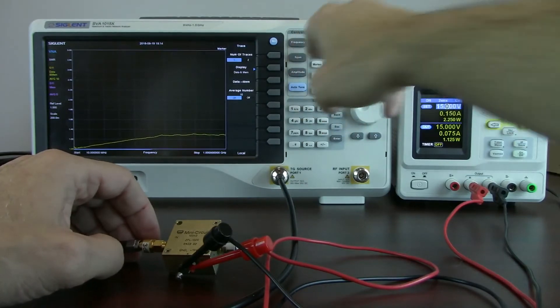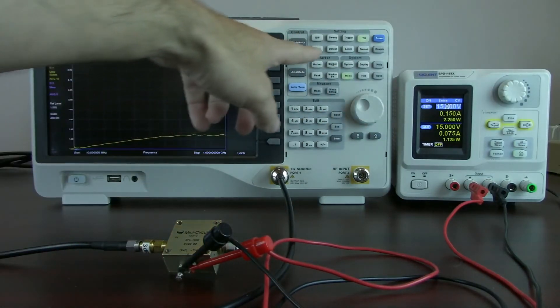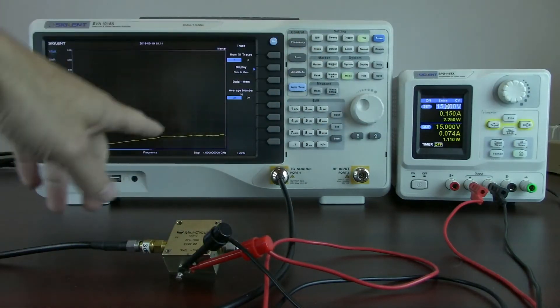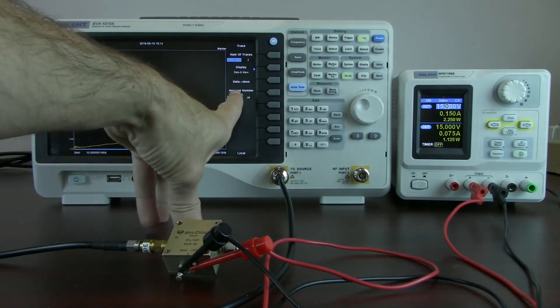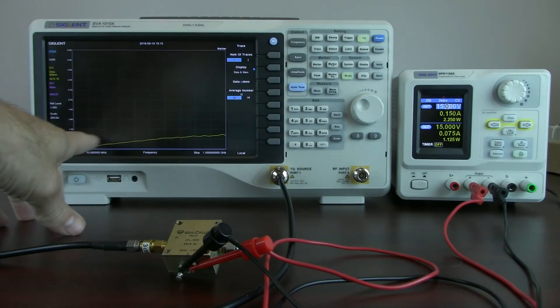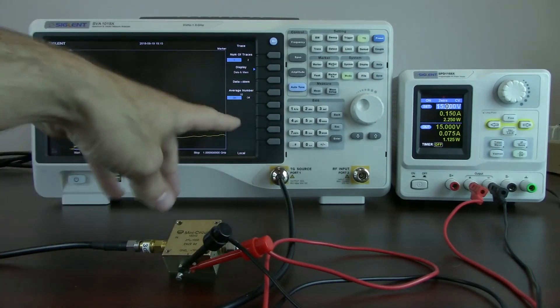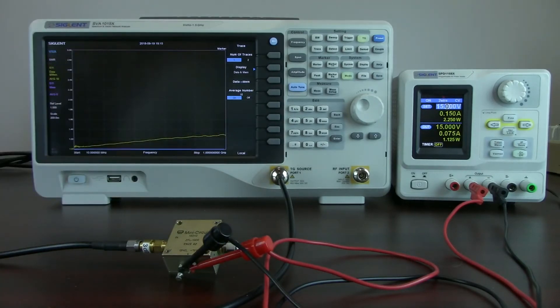So, by selecting trace, I can now pull in different trace values and show different traces on the display. I set the average number to 10. And so you could see we've got a nice curve here that's very, very close to what we see on the datasheet.